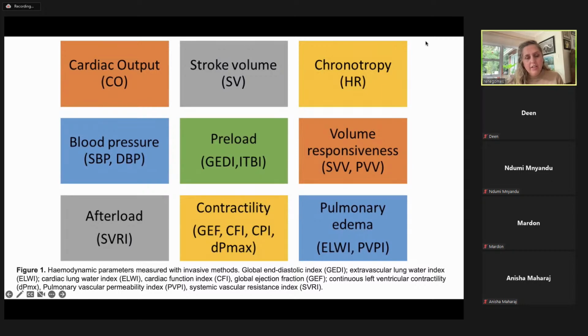I just wanted to share with you guys as well, they said to us in that cardiac output workshop that we could get the PPV on the monitor without a cardiac output monitor on, because we've of course got an arterial trace. As long as you've got an arterial line trace, you can get PPV. I didn't know about that at all, so I checked it out and it is true. I got it on, I can't remember if it was Drager or Philips, but I'm sure it's available on both. You just go into the actual module and you can just switch on the PPV, and it's very useful.